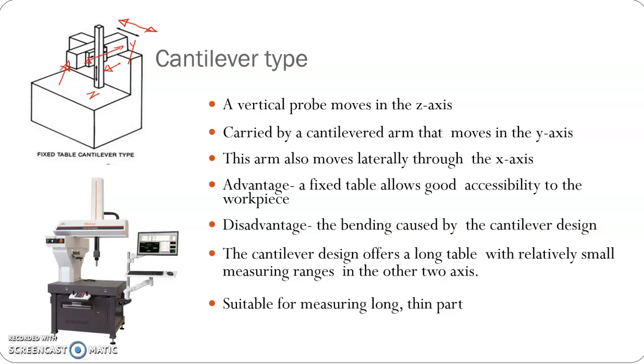The cantilever type is suitable for measuring long thin parts since it can have a long table with relatively small measuring ranges in the other two axes.